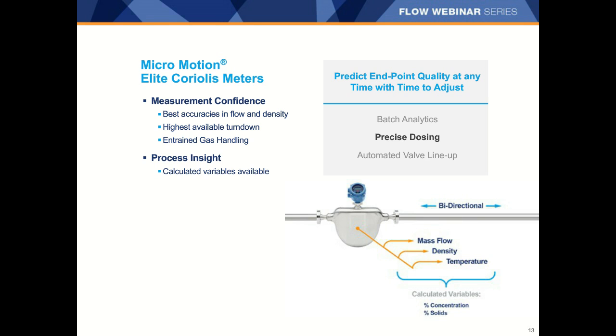What else can impact your charging or dosing accuracy? How about bubbles or entrained gas? When a pipe goes from empty to full to empty again, the transition period between those conditions will oftentimes be a large source of inaccuracy on the charge. But if a meter is better equipped to handle those transition periods when there is some entrained gas in a liquid, you will inherently have a better charge.